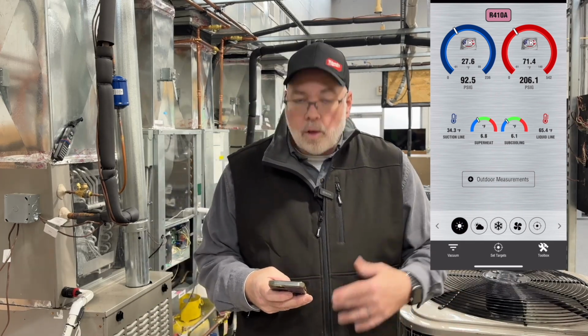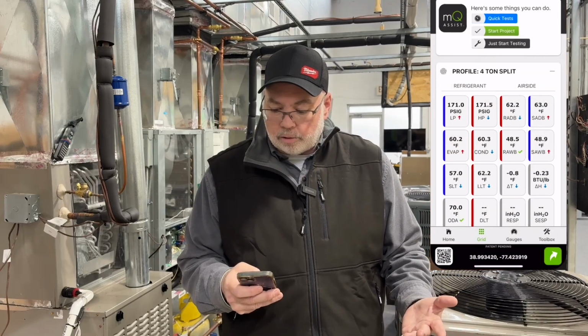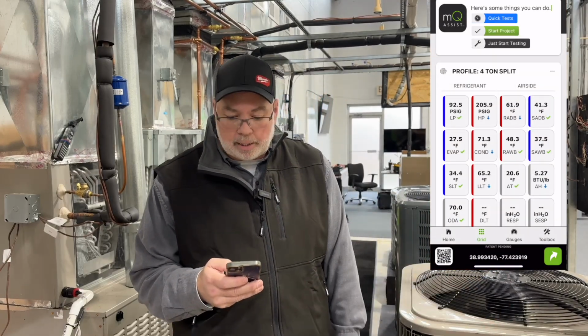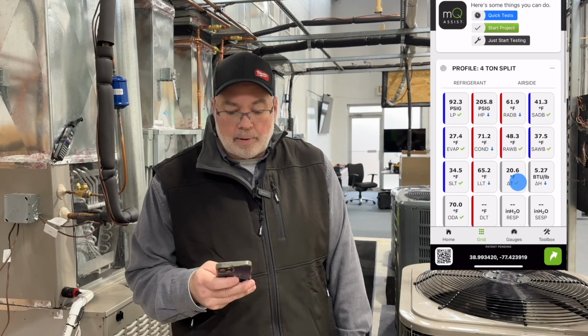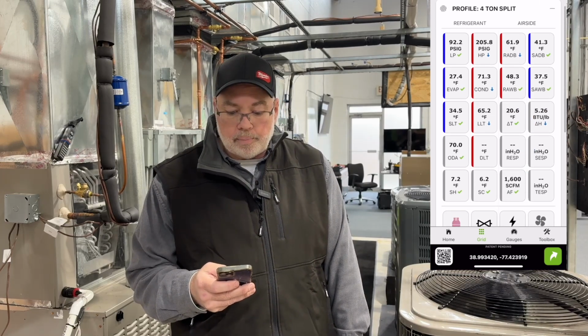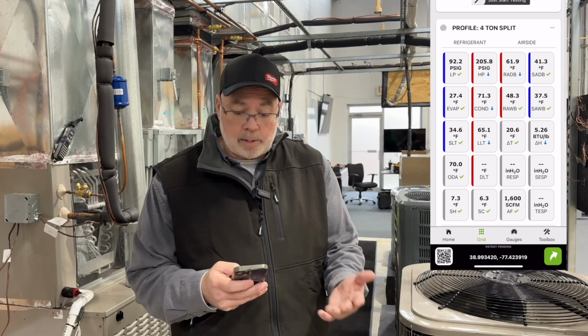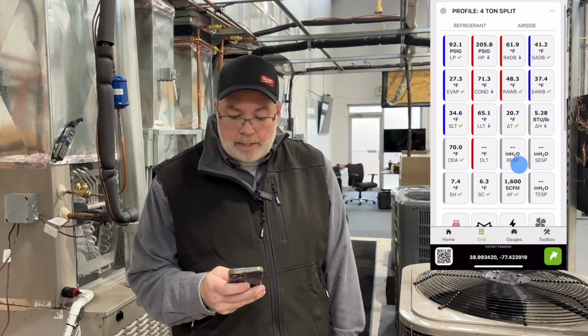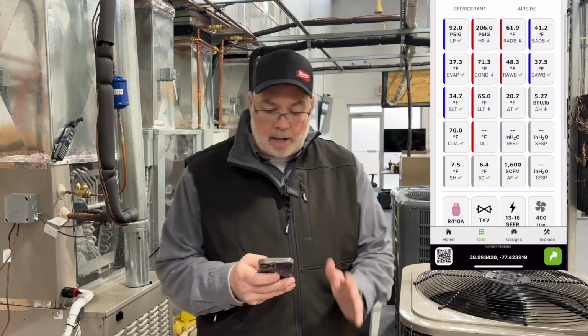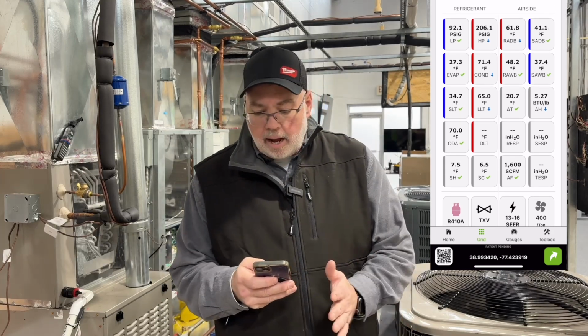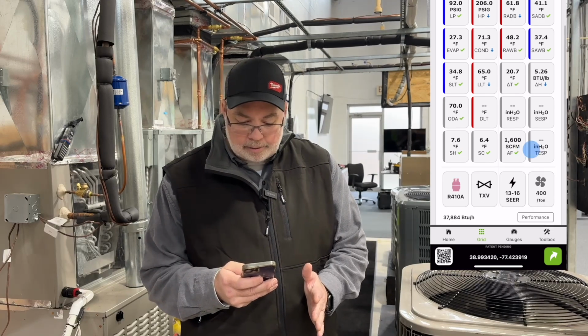You can take screenshots off this if you want and be able to save that and upload that to your tickets. Now, I'm going to switch over to Measure Quick. I have the tools connected to Measure Quick as well. What we're looking at right now is what we call our grid view. You can see that I've already profiled the equipment. It says 4-ton in the screen. And it shows our temperatures and our pressures, both on refrigerant on the left side, air side on the right.